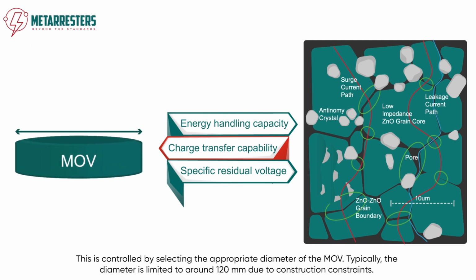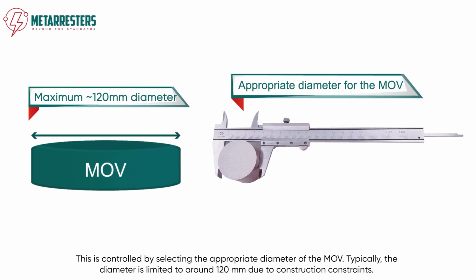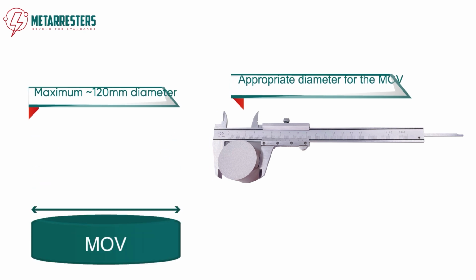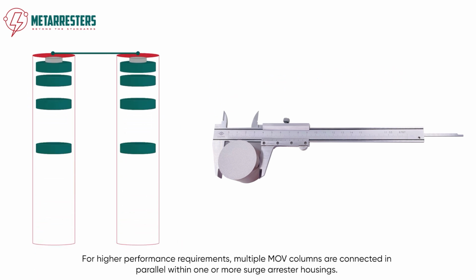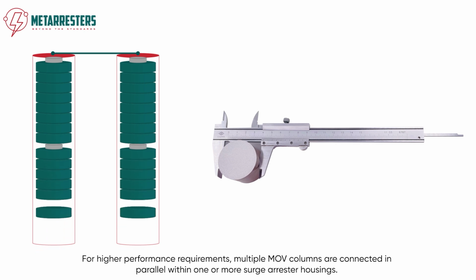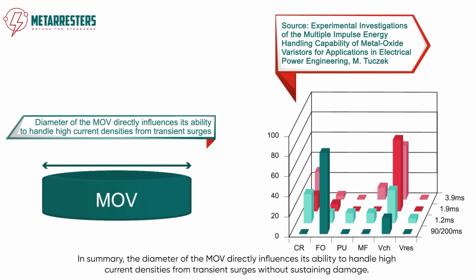This is controlled by selecting the appropriate diameter of the MOV. Typically, the diameter is limited to around 120 mm due to construction constraints. For higher performance requirements, multiple MOV columns are connected in parallel within one or more surge arrestor housings. In summary, the diameter of the MOV directly influences its ability to handle high current densities from transient surges without sustaining damages.